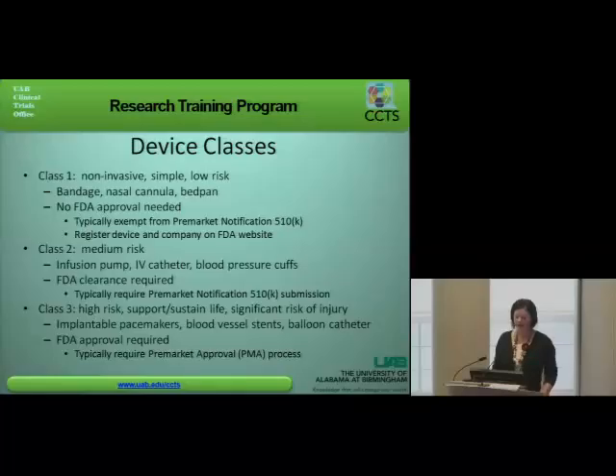The FDA considers devices to be in 3 classes. The first class is a non-invasive, simple, or low-risk device. It's typically a bandage, nasal cannula, or bedpan. There's no FDA approval needed for this type of device. It's typically exempt from the pre-market notification 510K process, which I'll talk a little bit more about in a few minutes. And they typically register the device and company on the FDA website.